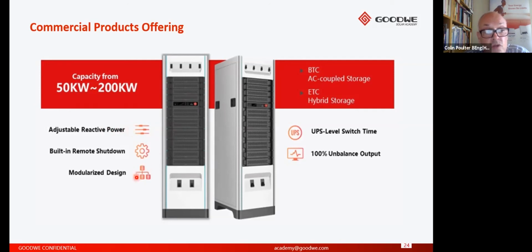It's a very modular design, as you can see presented here in these equipment racks, and UPS level switch time capability is also included, giving backup supply within a 10 millisecond operational range.